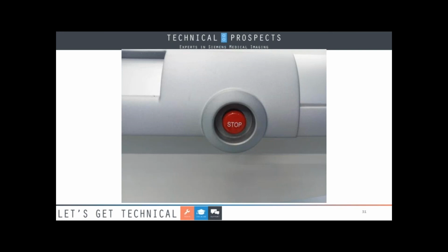Emergency stop errors can be very tough to isolate. There's usually more than one emergency stop button, and most event logs don't let you know which emergency stop button is being actuated. So if you have an emergency stop issue, the first thing you're going to want to do is ohm out each button.